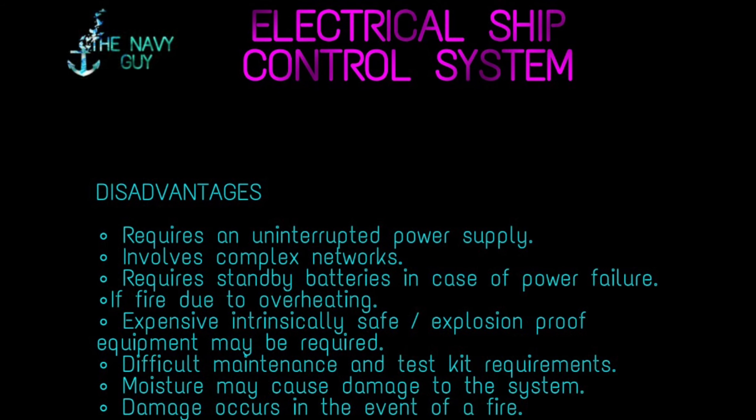Some disadvantages of the electrical ship control system are: the system requires an uninterrupted power supply with no voltage fluctuations; it involves complex networks; it requires standby batteries in case of power failure; there is a risk of fire due to overheating; expensive intrinsically safe, explosion-proof equipment may be required; maintenance is difficult with test kit requirements; moisture may cause damage to the system; and damage readily occurs in the event of a fire.